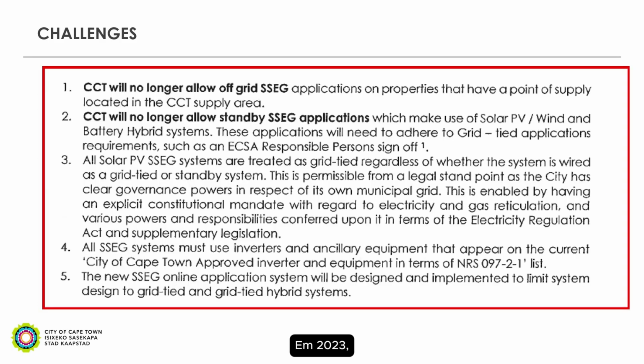So what we've done in 2023, after our challenges with all of these off-grid systems and non-approved inverters, we no longer, since October 2023, allow it to be connected to our network. We insist on only grid-tied approved inverters. We also no longer allow standby SSEG applications which make use of the solar PV or hybrid systems. And then we also treat all our systems as grid-tied, regardless if the system is wired as a standby system.